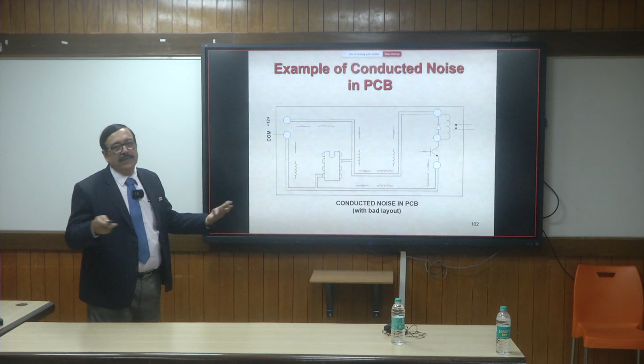done judiciously. You may have more than one trial to execute the system. For the stray inductance problem in large systems, we go in for sandwich bus bars. Suppose we make 200 kilowatt inverters, we go in for a sandwich bus bar system. It's a replica of a PCB. We have an insulating dielectric in between, usually fiberglass. Then we have a copper sheet on the top and a copper sheet at the bottom. So it's a total sandwich system, and then you fit your components from the bottom side. Fitting the component is not going to be easy, so you have to do a lot of engineering, because this component, whatever it is, has to get connected to the lower bus, so you have a lower lead length. This is going to get connected to the top bus, so it has a higher lead length.